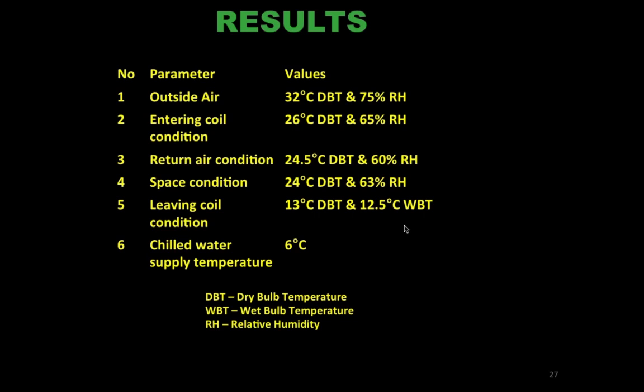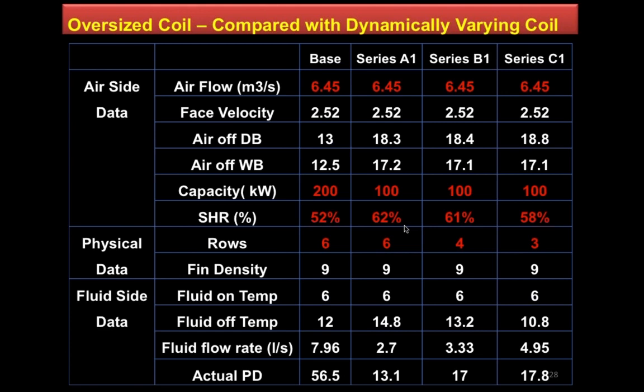So one strategy I'm going to discuss with you now is how we can work with these changing requirements of the coil size. The other one I'm going to discuss is how we can optimize the coil parameters in terms of the delta T through the coil, the fan speed, in other words the volume of airflow, and so on and so forth. Let's look at the first aspect, an oversized coil in which we can have a dynamic change of the effective surface area in the operation stage. This is being done through a simulation study.